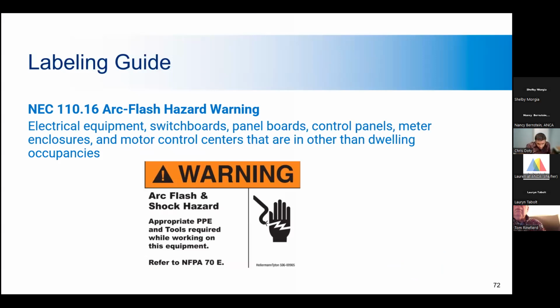So here we have your standard arc flash and shock hazard label. It's required on electrical equipment, switchboards, panel boards, control panels, meter enclosures, and motor control centers that are in other than dwelling occupancies. Arc flash hazards or warnings are very important because arc flash incidents can cause death, and if not, they can cause serious injury.